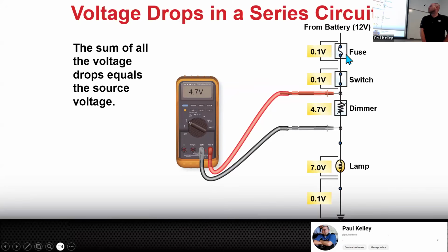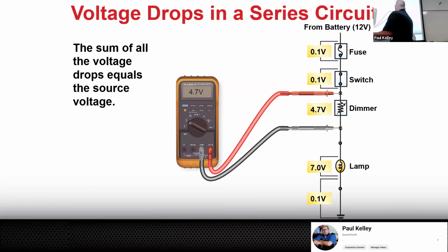So if I'm measuring voltage drop of a fuse, I'm expecting 0.1 or maybe less. 0.1 or less would be pretty good. So if you look at that right there, 0.1 on the fuse and 0.1 on the switch, those are both good, right? But I'd move the leads together. 0.1 on the fuse, 0.1 on the switch.